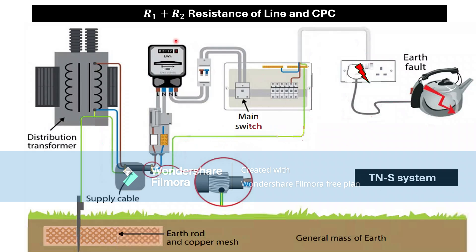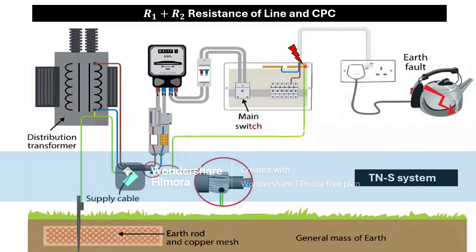R1 plus R2 is the internal resistance of the line and CPC. If we measure the resistance of the line and earth from the final point — because at the final point we get the highest resistance — for example, if you have 10 radial sockets, the 10th socket furthest from the distribution board gives the highest resistance of line and CPC. R1 is the resistance of the line and R2 is the resistance of the CPC from the distribution board to the furthest point.